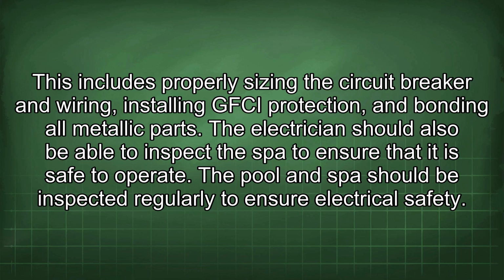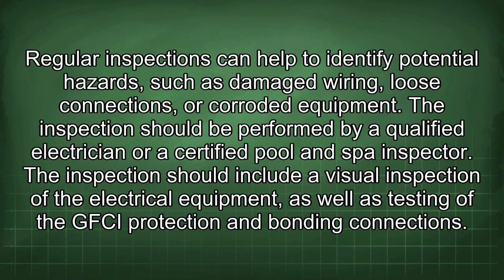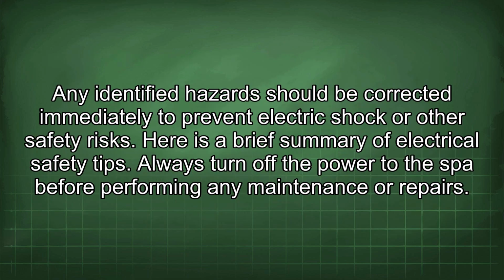The pool and SPA should be inspected regularly to ensure electrical safety. Regular inspections can help to identify potential hazards such as damaged wiring, loose connections, or corroded equipment. The inspection should be performed by a qualified electrician or a certified pool and SPA inspector. The inspection should include a visual inspection of the electrical equipment, as well as testing of the GFCI protection and bonding connections. Any identified hazards should be corrected immediately to prevent electric shock or other safety risks.